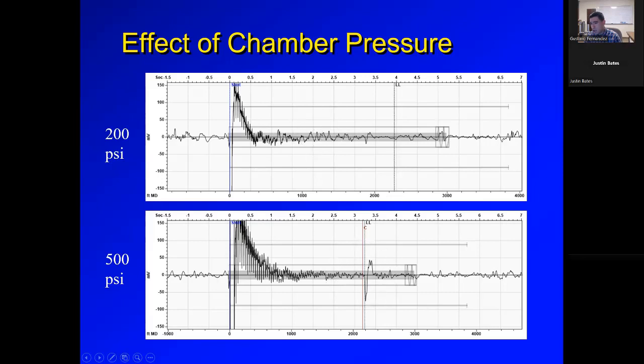When you apply more pressure for the next shot and shoot again, it goes from this to this. Now you have a much clearer liquid level peak, simple for the software to pick. It was there before, but so small you couldn't see it. Now it's bigger because the energy is more, so reflected energy from the liquid level is more. The microphone picks up that echo, and we can see collars all the way down to the liquid level. So it goes from a trashy quality fluid level, because of the low pressure differential, to an excellent fluid level shot.